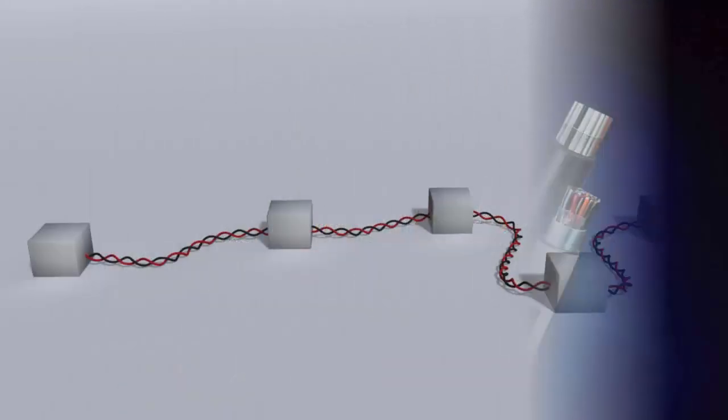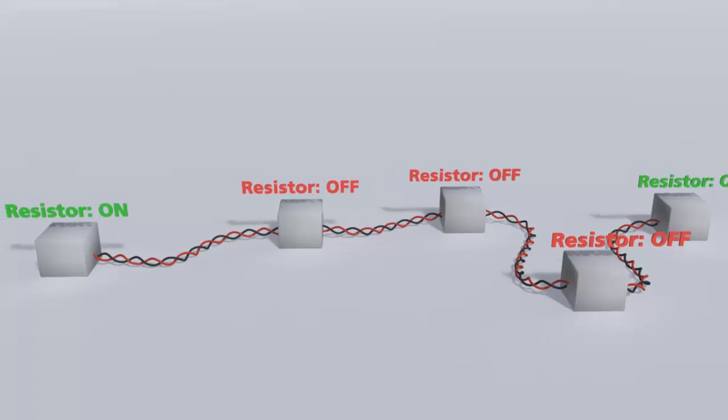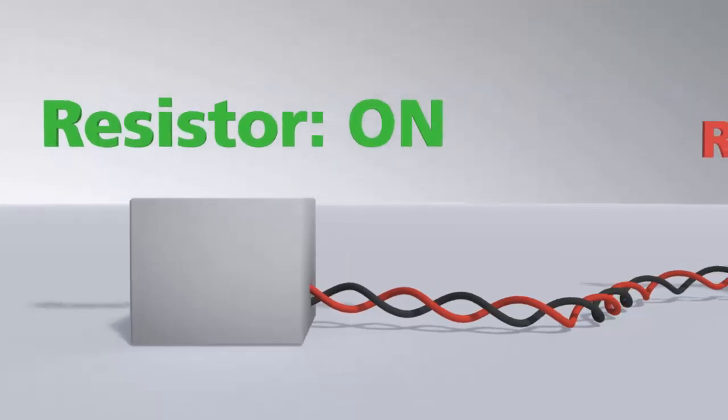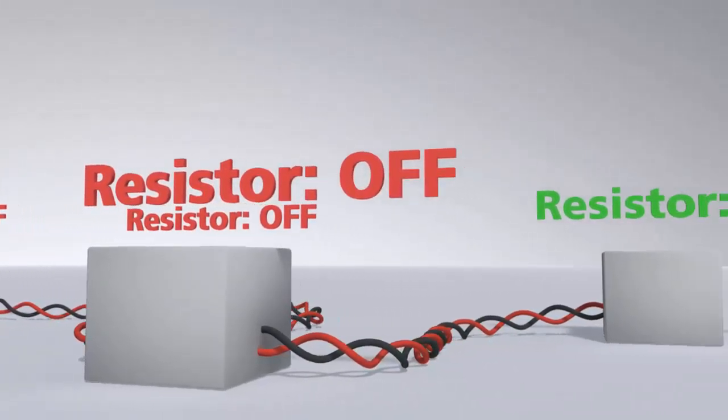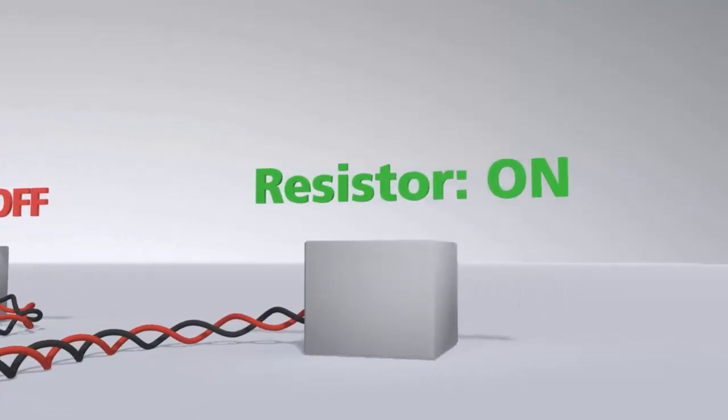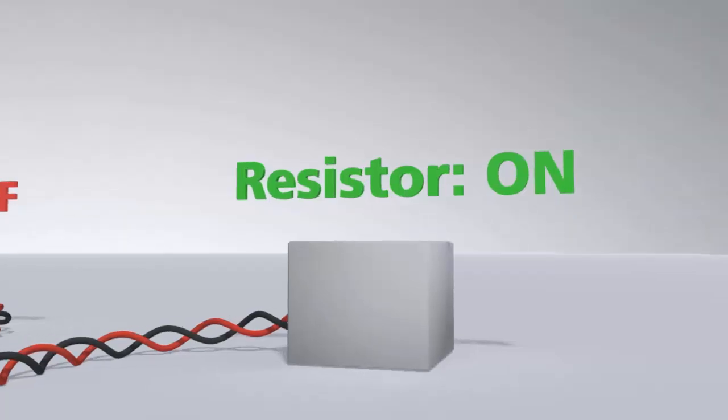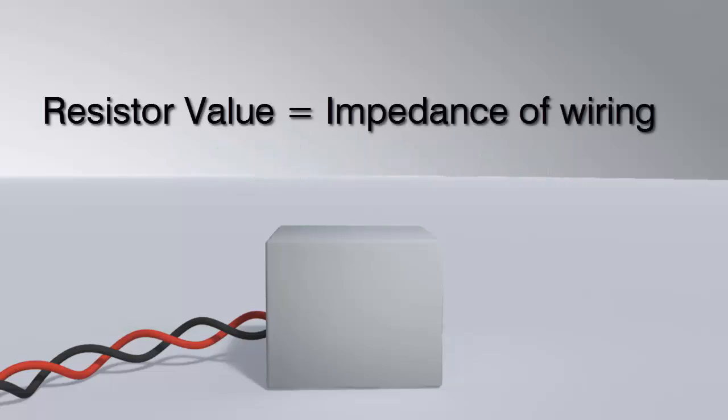On a network with proper topology, you only need termination resistors at the two extreme ends of your network in order to prevent signal reflection from an open circuit. Some devices have a resistor built-in. If you use such a device and the resistor is engaged, it should only be placed at the extreme ends. If your devices do not have built-in termination, note that the value of each resistor should be equal to the characteristic impedance of the wiring, typically 120 ohms for twisted pairs.